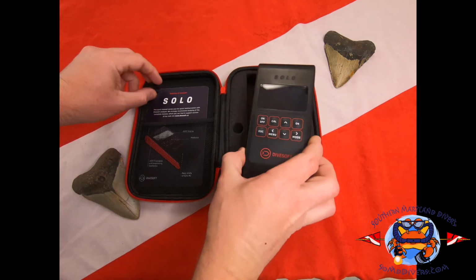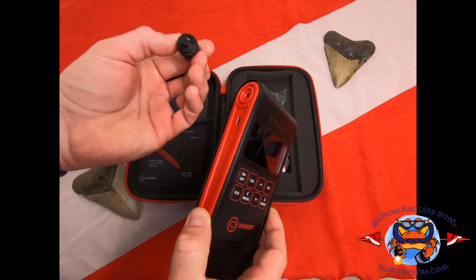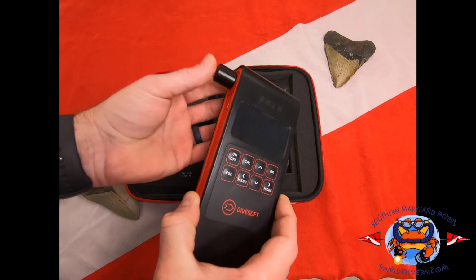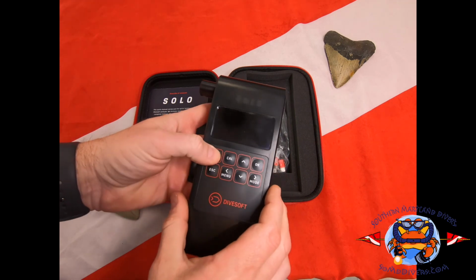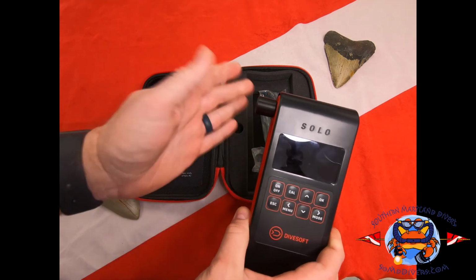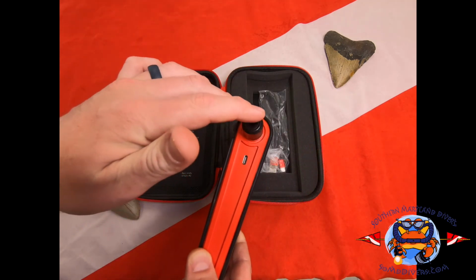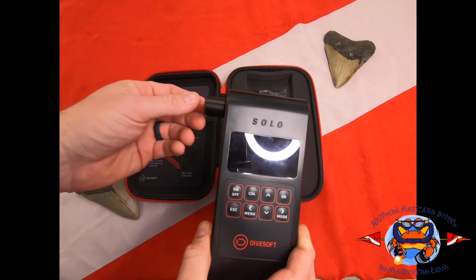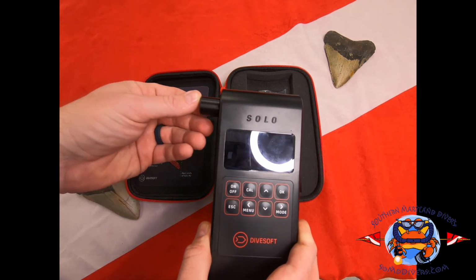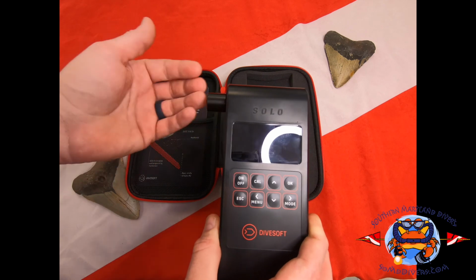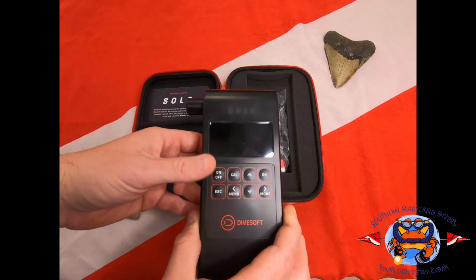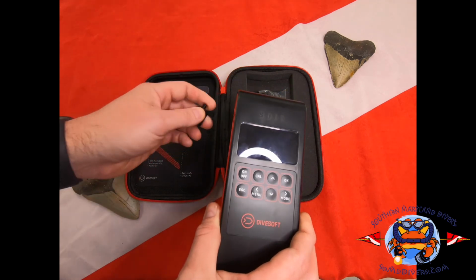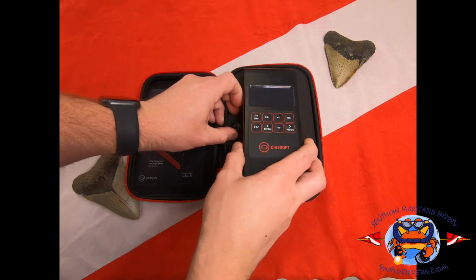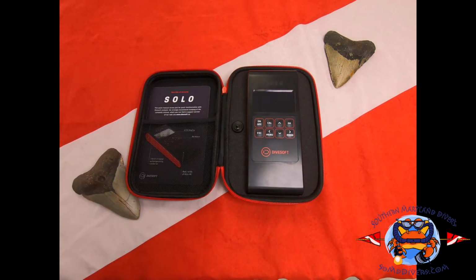Again, like I mentioned earlier, this is the adapter, the flow restrictor. So you would plug this in, turn this on, make sure it's calibrated, and then this piece right here would get sealed. There's an O-ring here that would get sealed up against the tank valve, and you would flow just a light flow of whatever the mix is through, and then you get your final oxygen content and helium content in the results. So that's the Solo analyzer.